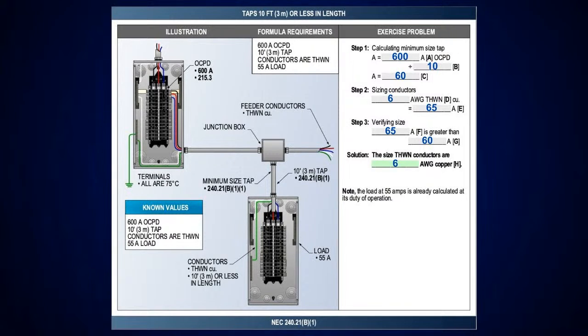Everybody should have these taps down pretty well now. But here in the illustration, I've got a 600 amp overcurrent device upstream. I'm going to make a tap off of that feeder circuit that's going out. So I'm going to divide that by 10. That'll give me 60 amps.